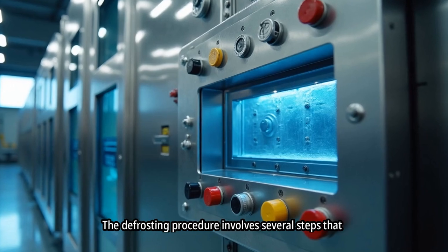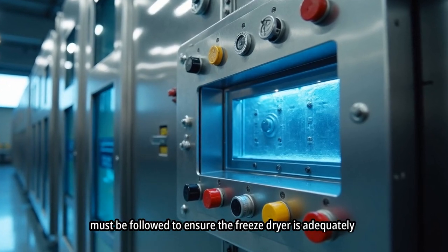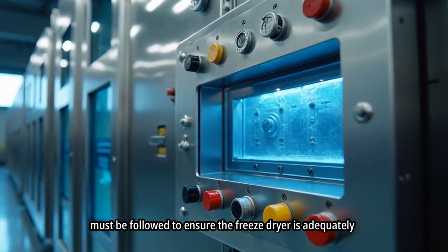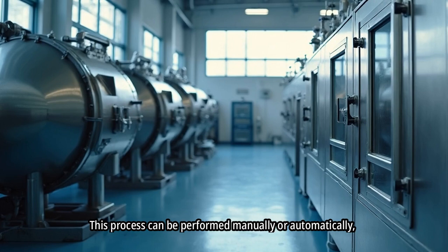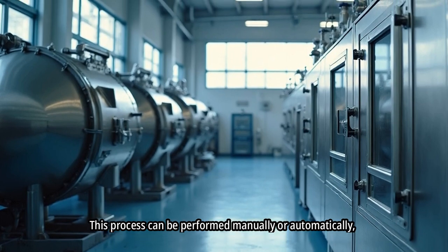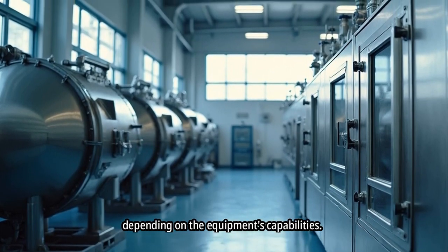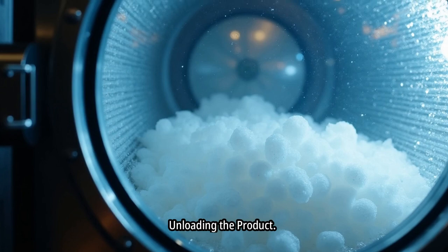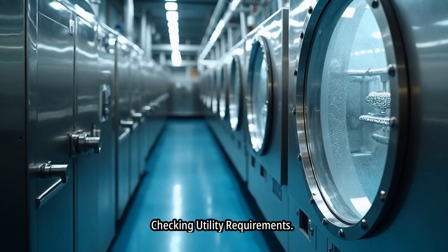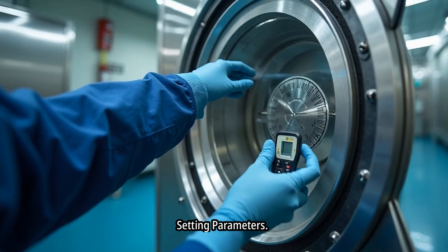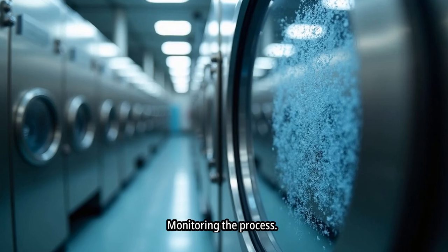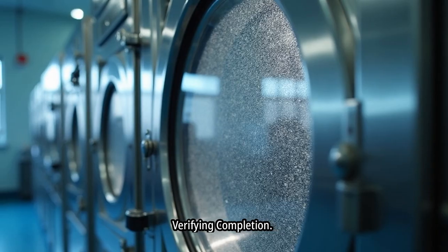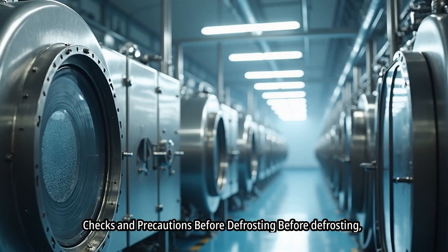The defrosting procedure involves several steps that must be followed to ensure the freeze dryer is adequately maintained. This process can be performed manually or automatically, depending on the equipment's capabilities. Key steps involve unloading the product, checking utility requirements, setting parameters, starting the defrosting cycle, monitoring the process, verifying completion, checks and precautions before defrosting.